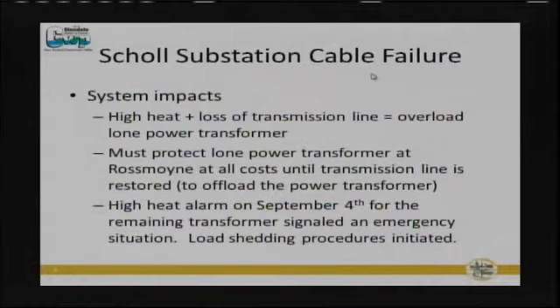The system impact, high heat, and loss of transmission lines overloaded the lone power transformer at the Rossmoyne station that we had operating. It was critical that we protect that transformer. If we had lost it, it likely would have affected greater than 50%, probably closer to 60%, of the city, and replacing it would have taken substantial time. So at all costs, we wanted to maintain and protect that one transformer.